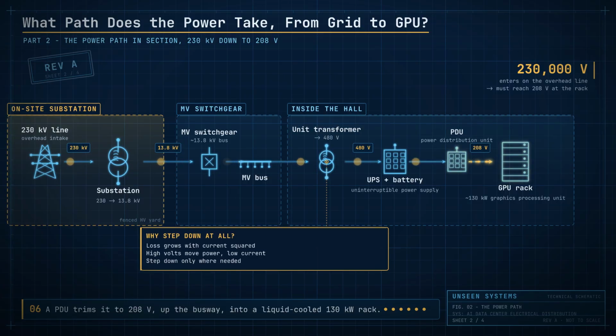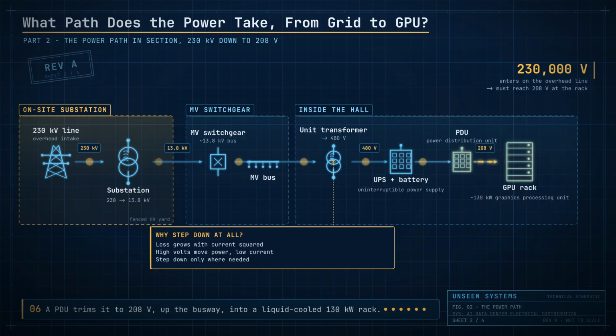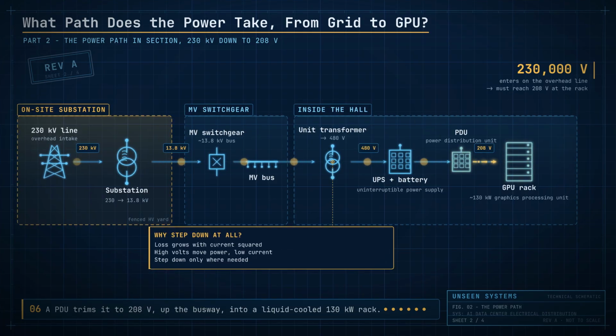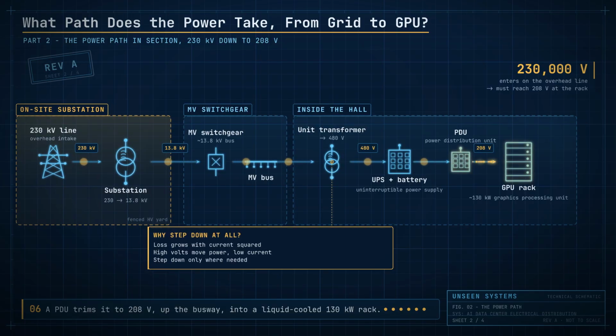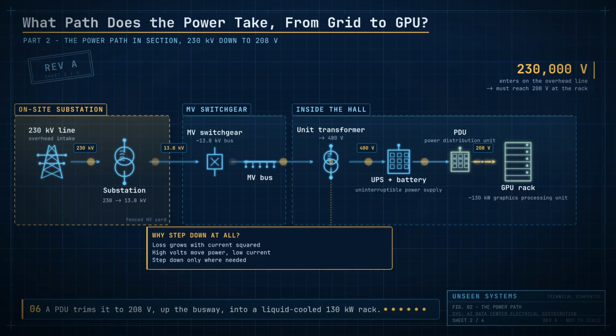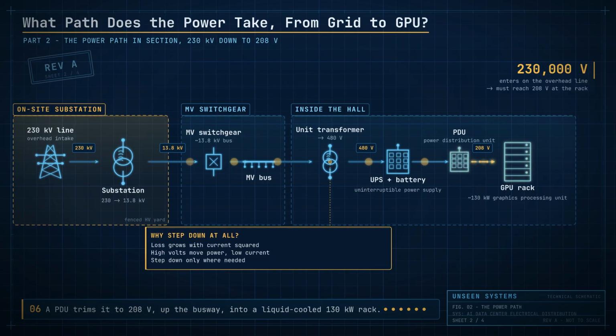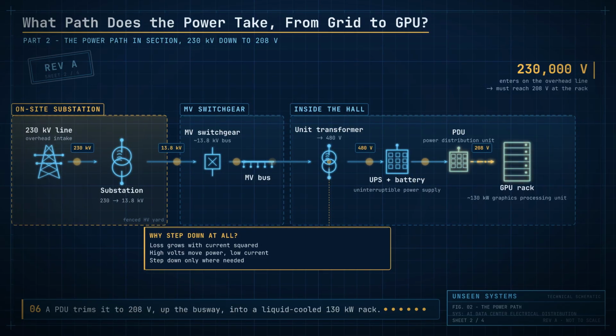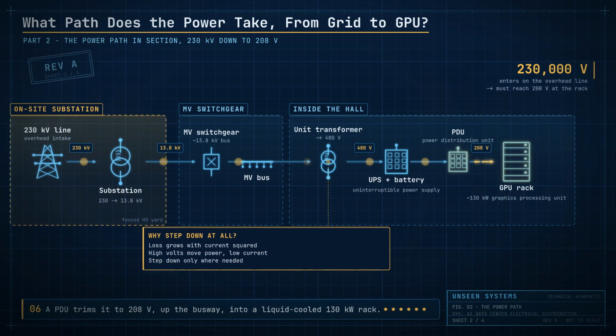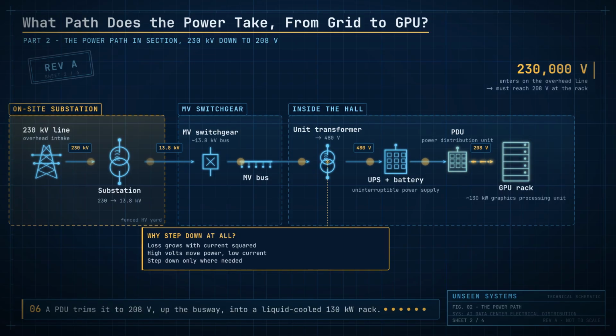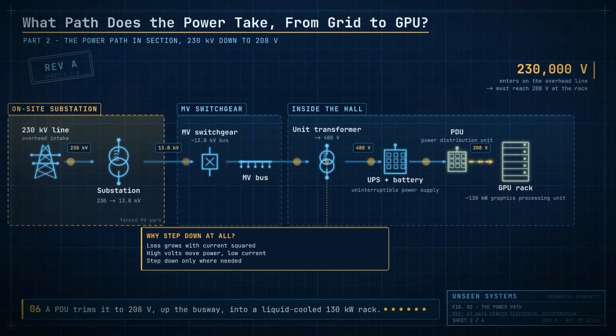So why step the voltage up and down all the way along that path? To fight one equation: line loss equals current squared times resistance. Push the voltage high and the current falls, and the wasted heat falls with the square of it. So you move power at high voltage and low current over distance, and only drop it to low voltage, high current, right at the load. That whole chain of transformers exists to obey that single rule.